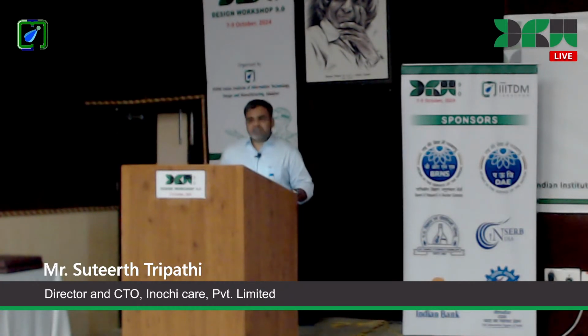One of the challenges within this device was to control the suction part of it, that is the negative pressure part, and the oxygen supply part, so that the wound is in low pressure but still rich in oxygen. The oxygen supply should not go out directly into the suction unit, so that the volume of oxygen there itself is able to aid the patient. The other challenging part was to control the flow rate of the oxygen as well as the suction rate and suction pressure in such a way that providing the oxygenation does not reduce the pressure that we are applying, and providing the suction does not reduce the amount of oxygen that we are supplying.